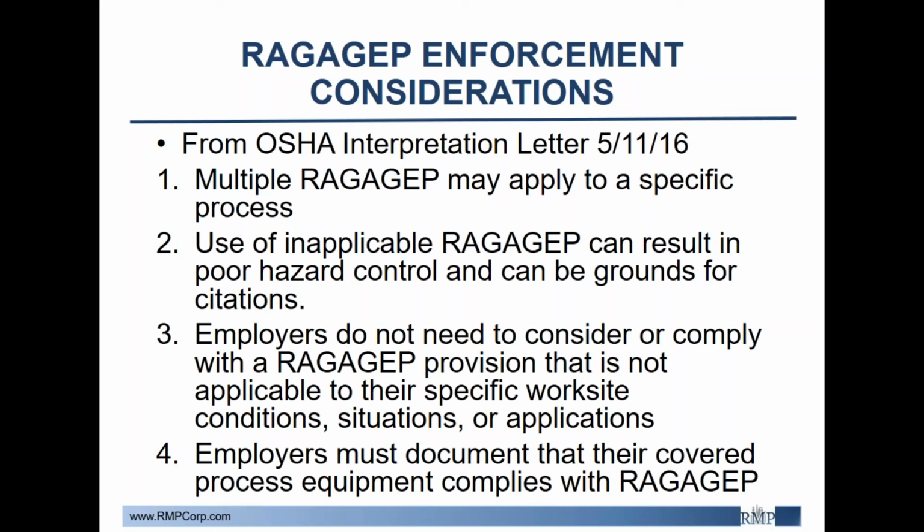For example, API 520 or ISO standard number 4126-9 are both RAGAGEP for relief valve installation and contain similar but not identical requirements. Both documents are protective and either is acceptable to OSHA. So again, as we mentioned, based off the site-specific conditions, you can choose the standard that you feel better applies to your process.